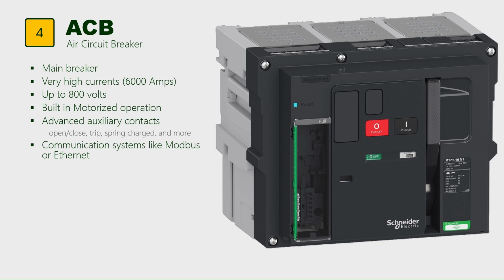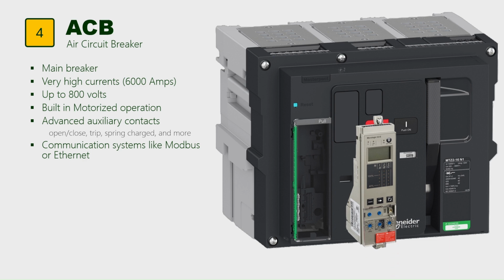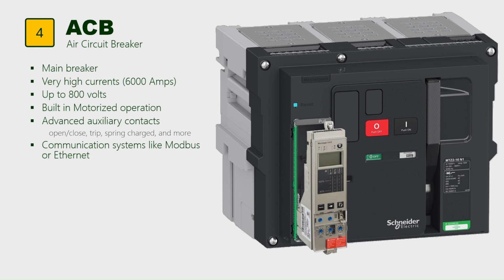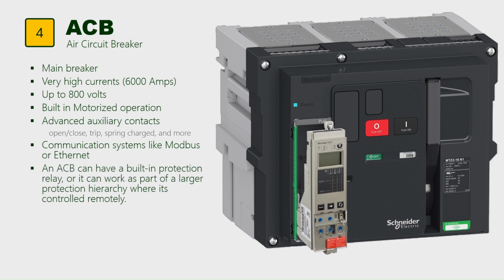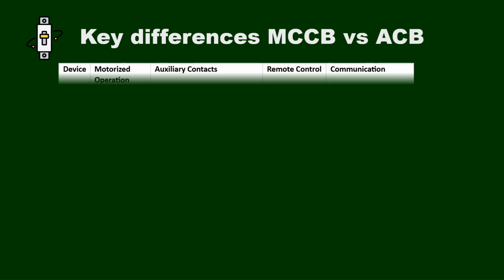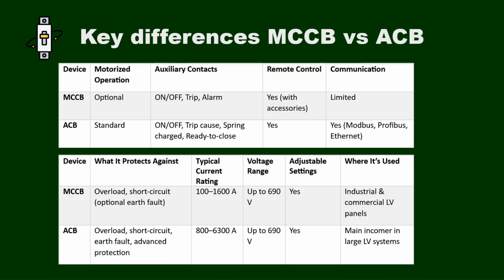Many ACBs even support communication systems like Modbus or Ethernet, so they can send detailed information to SCADA or building management systems. An ACB can have a built-in protection relay, or it can work as part of a large protection hierarchy where it's controlled remotely. This table highlights the key differences between MCCBs and ACBs. You can pause the video anytime to examine it more closely.